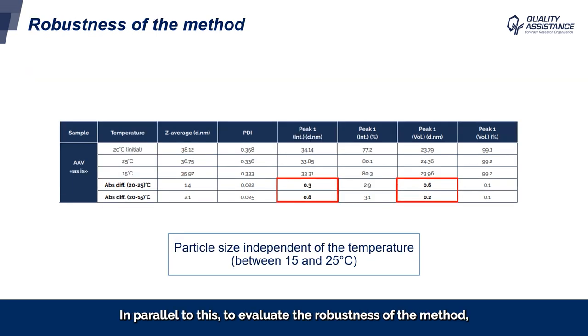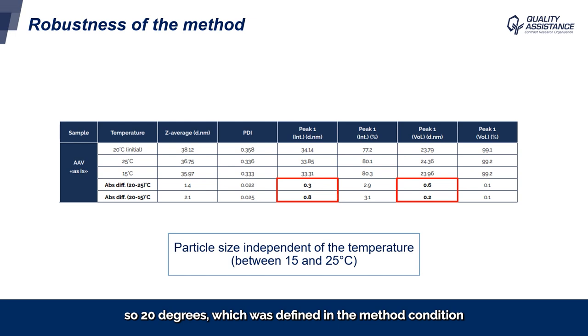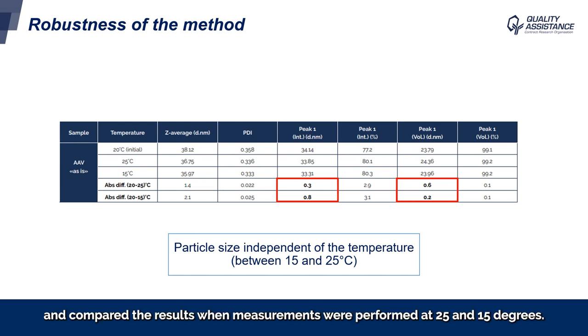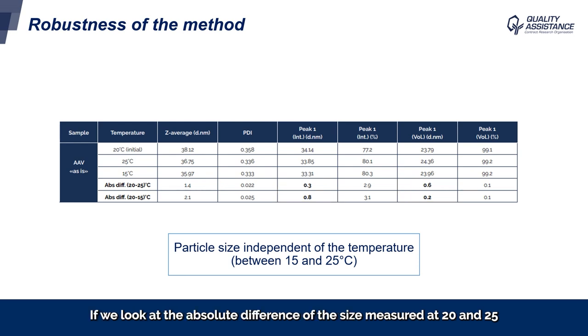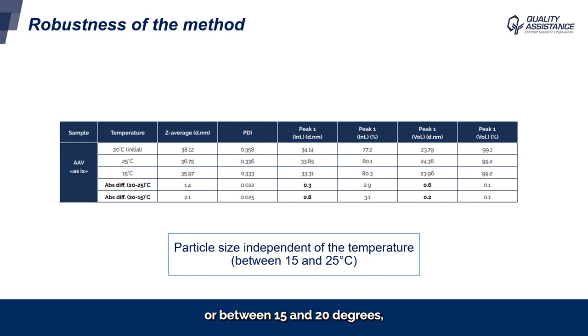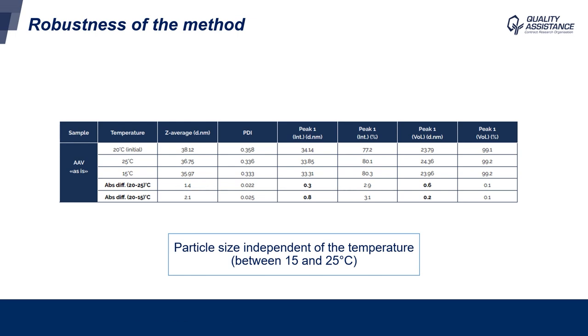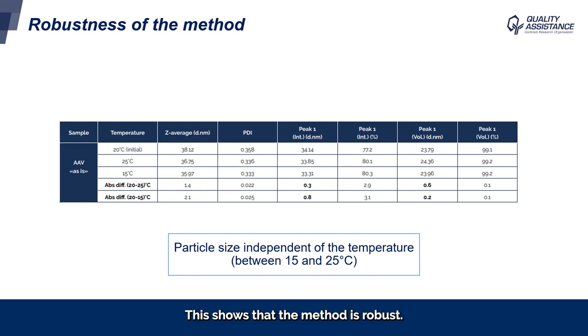In parallel, to evaluate the robustness of the method, we performed the analysis at three temperatures: 20°C, which was defined as the method condition, and compared the results when measurements were performed at 25 and 15°C. Looking at the absolute difference in size measured between 20 and 25°C, or between 15 and 20°C, both by intensity and by volume, we see that this difference is minor and negligible. This shows that the method is robust.